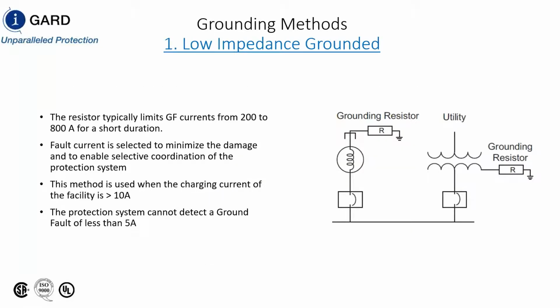So why we use a low resistance grounded system, and the amount of current that you choose, or the customer chooses, for a low resistance grounded system has to do with how much capacitive charging current you have, for one thing. So if your capacitive charging current is over 10 amps or over 20 amps, then you need to go with the low resistance grounded system. With a low resistance grounded system, you have to now look at your protection system.